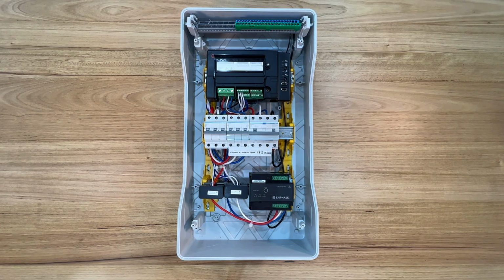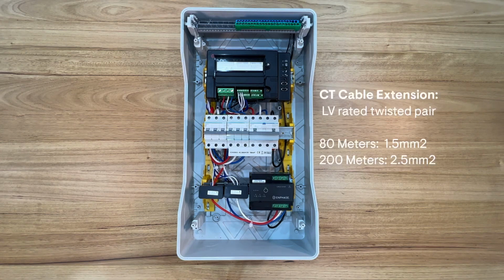Often mistakes are made wiring these 3-phase consumption CTs. Be sure to confirm phase continuity and direction of the CT itself, as the consumption CTs will be located elsewhere, for instance connected around the main AC supply cable at the main switchboard of the site. So a good idea here is to label each end of the CT flying lead, and you can extend CT cables up to 200 meters wiring distance. This enables you to have a lot of flexibility with your installation of the IQ gateway.